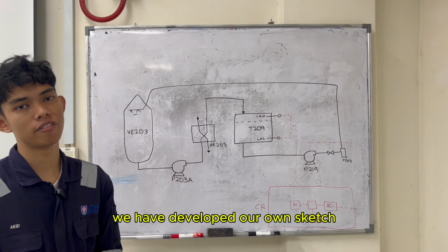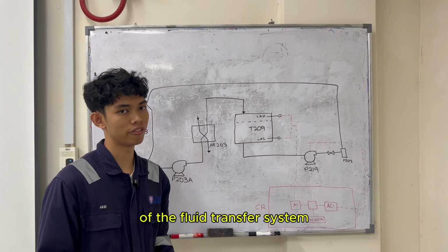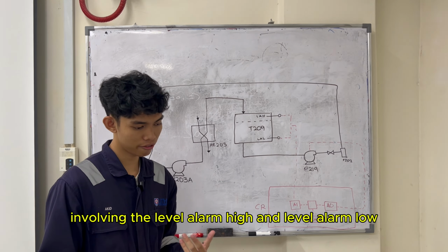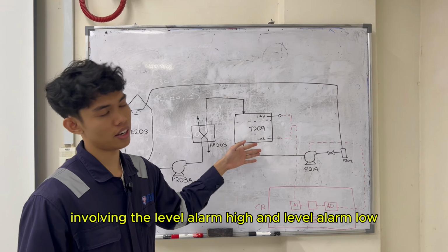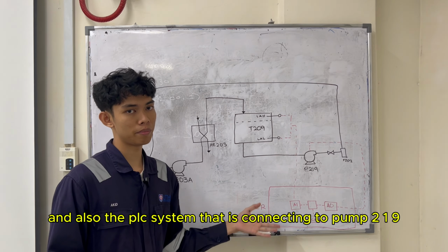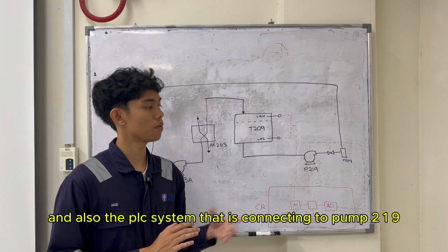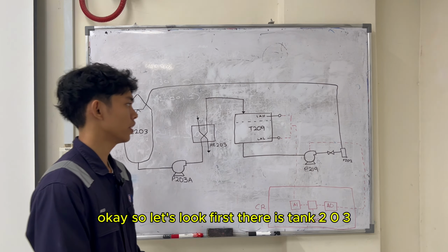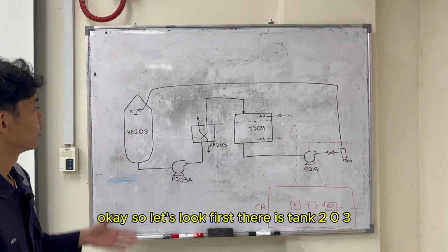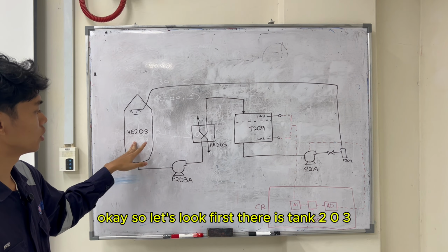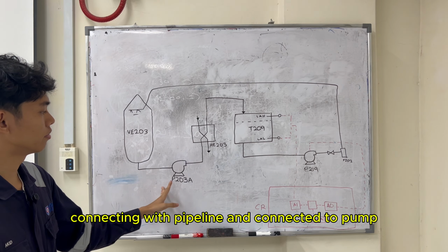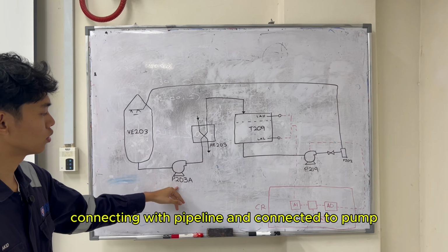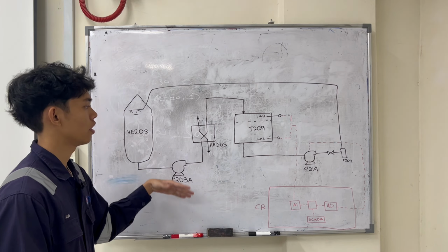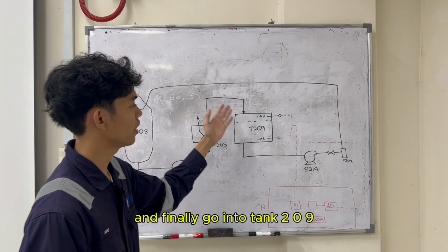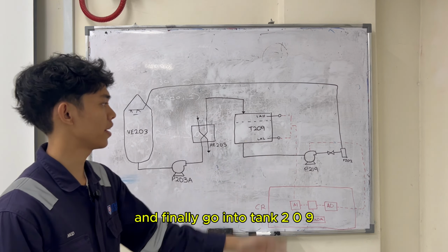Okay, so we have developed our own sketch of the fluid transfer system involving the level alarm high and level alarm low, and also the PLC system that is connecting to pump 219. Okay, so let's look. First, there is tank 203 connecting with pipeline and connected to pump 203. And it will go to the heat exchanger and finally go into tank 209.